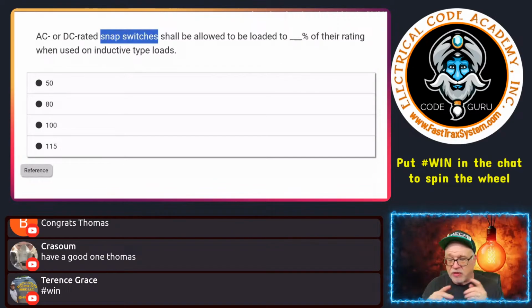So this is a snap switch. Now, you could go to the index, and under switches it will probably have AC or DC snap switches. But for me, I'm thinking this is a general requirement, it should be up in the front, so I am going to go to 404. I'm going to bold scan it because I've got enough information to scan quickly, and switches is not a massively large article. Plus I'm looking for a percentage value, the words 'inductive type loads,' and 'AC and DC snap switches.' That's going to make it pretty quick for me.